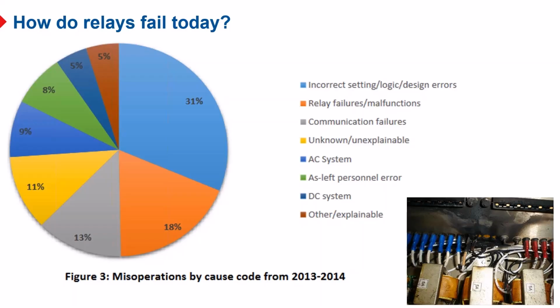And PRC-005 started out, of course, like most administrative initiatives, pretty simple. All the initial PRC-005 said was, you have to have a plan for testing your protective relay system, and you have to follow your own plan. And as simple as that sounds, utilities did a pretty bad job of it. PRC-005 was actually the most frequently violated protection reliability standard that NERC had. And over the years, every couple of years or so, they revised the standard, and right now PRC-005-7 is coming into enforcement. And as you can probably imagine, at each step, additional requirements were added.